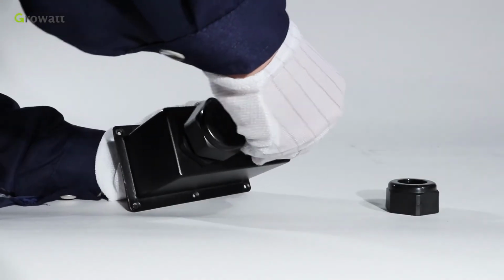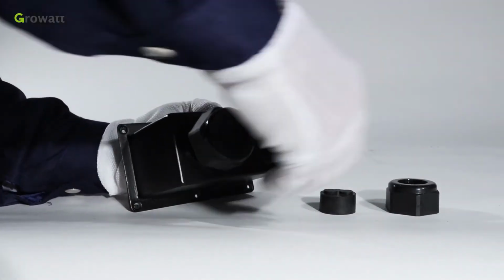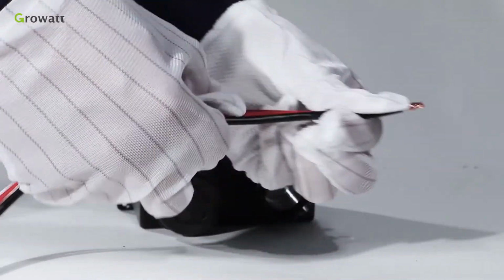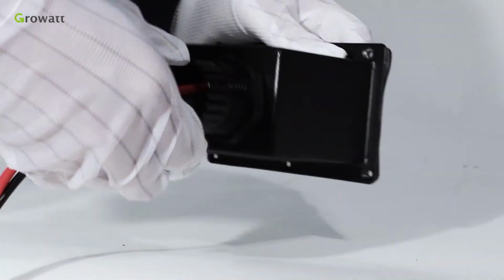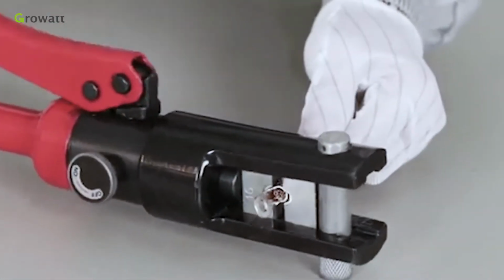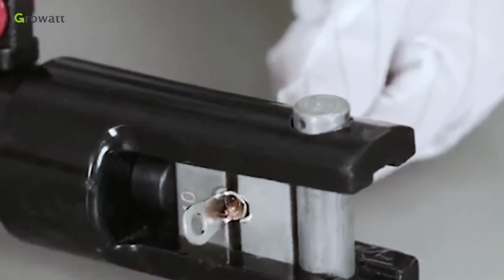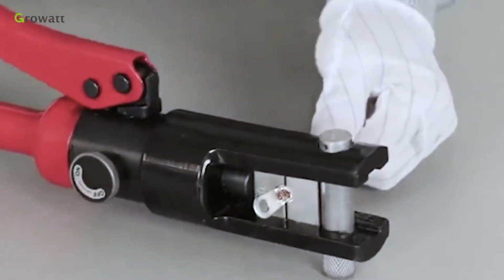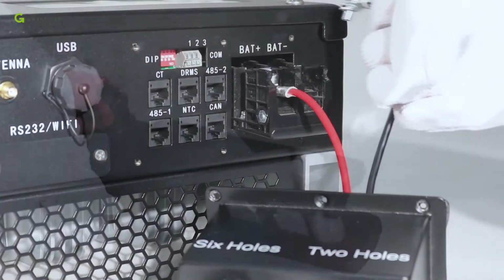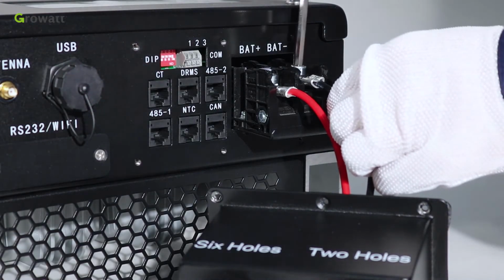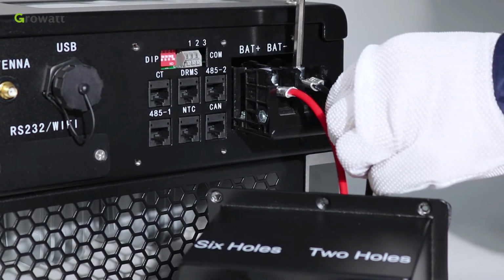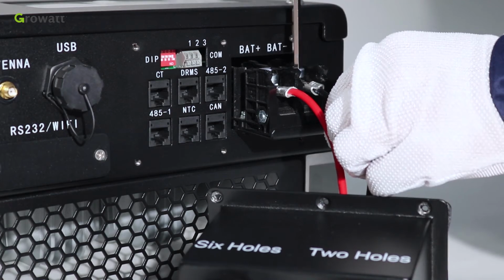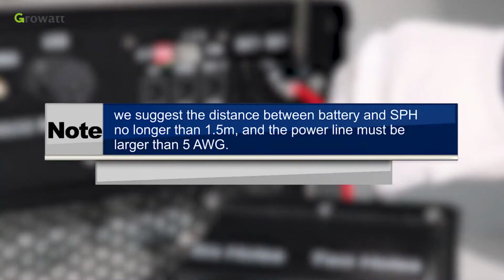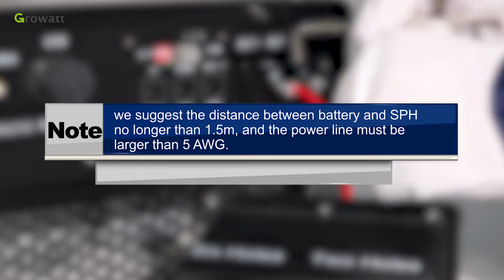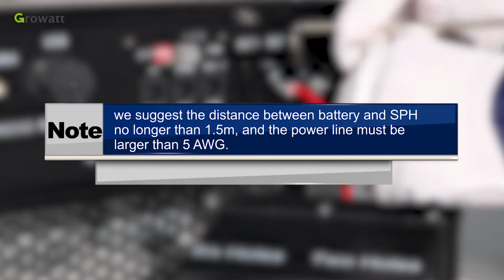Dismantle the waterproof cover. Thread cables through pressure screw, seal ring, threaded sleeve, waterproof cover. Thread cables into connection terminal, then press the terminal by relevant tools until the battery cables are firmly connected. Finally, connect positive and negative pole of battery cable to the respective battery terminal of SPH.